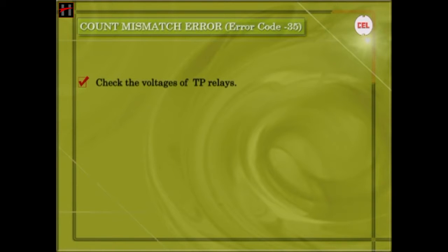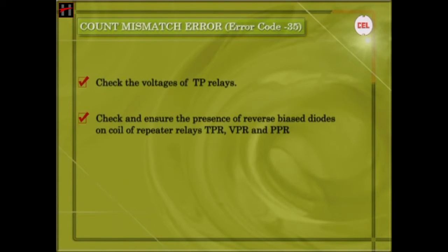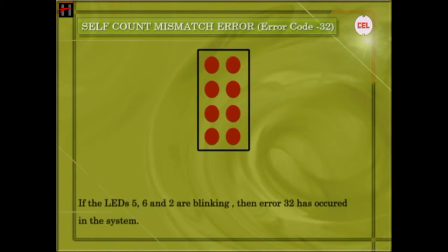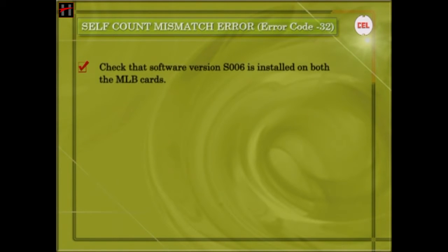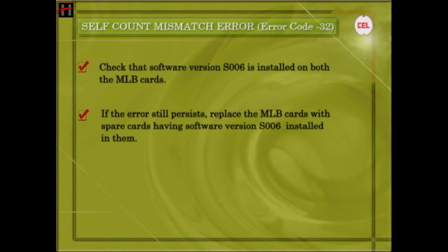Check the voltage of the TP relays and check the presence of the reverse bias diodes on the coil of repeater relays TPR, VPR, and PPR. Self-Count Mismatch Error: If the LEDs 5, 6, and 2 are blinking, then Error 32 has occurred in the system. This error occurs when software detects the counts of the MLB cards in the local unit. To rectify: first, check and ensure that software version S006 is installed in both MLB cards; second, if it persists, replace the MLB card with spare cards having software version S006 installed.